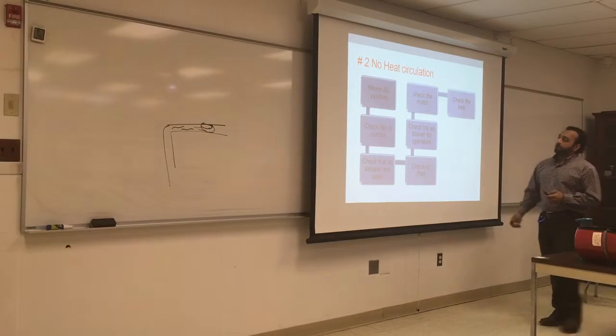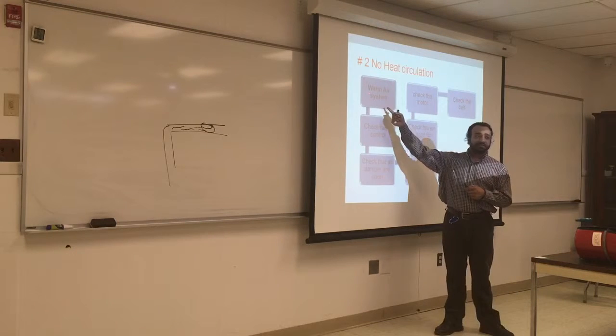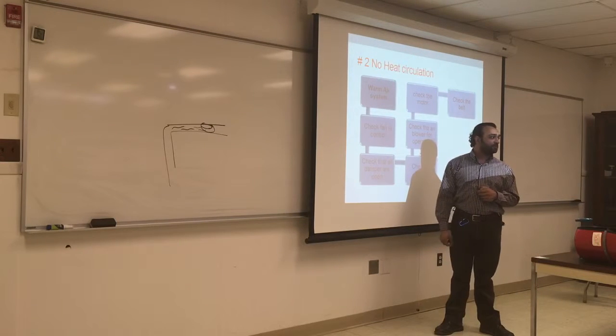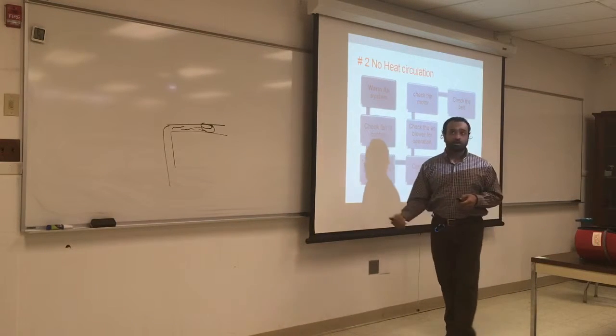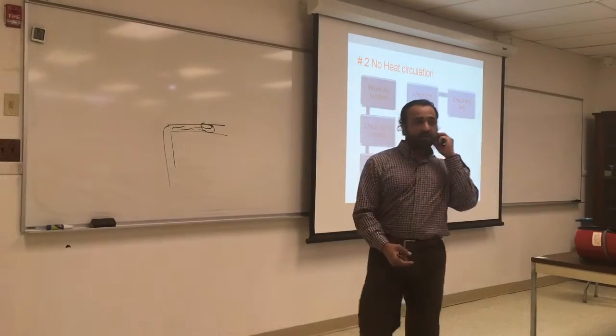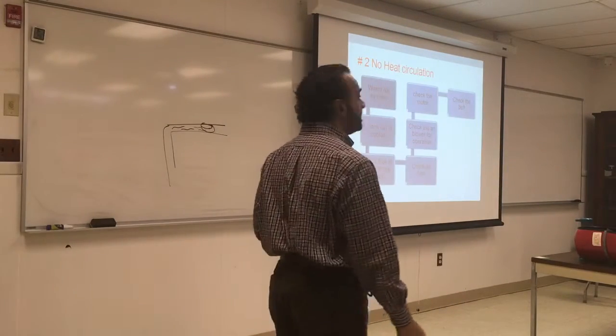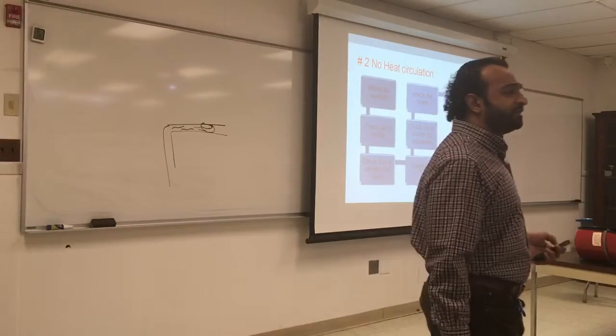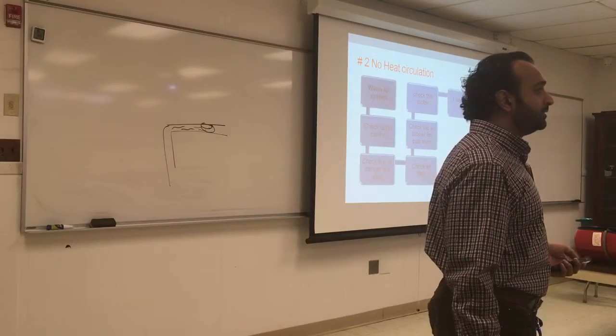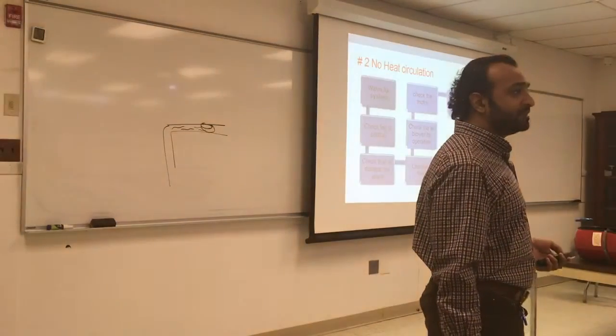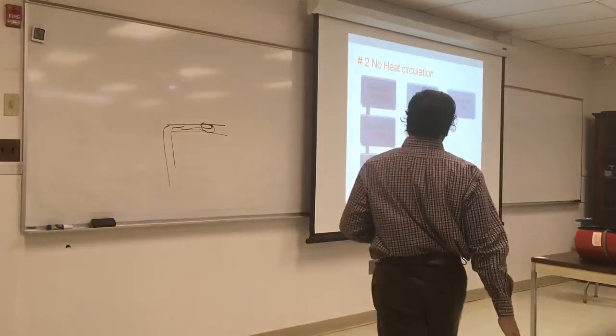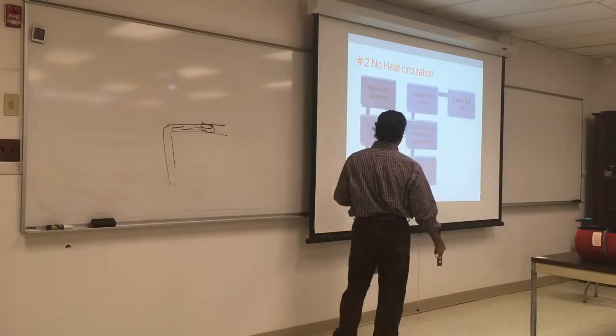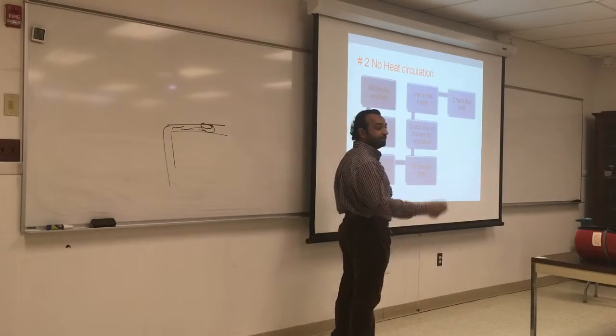Again, no heat circulation, but this time it is the warm air system. This happens a lot. So for hot water, you want to circulate water. For hot air, you want to circulate hot air. What circulates hot air through the duct system? Fan, inducer fan. So check the fan limit control. Make sure the limit is okay.